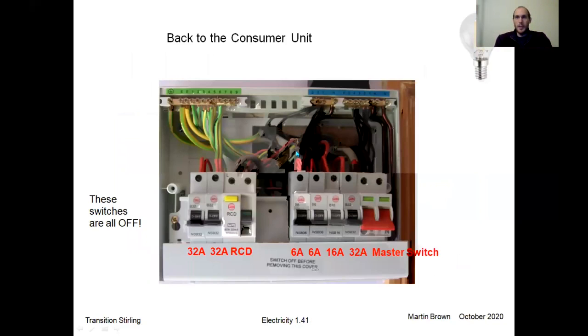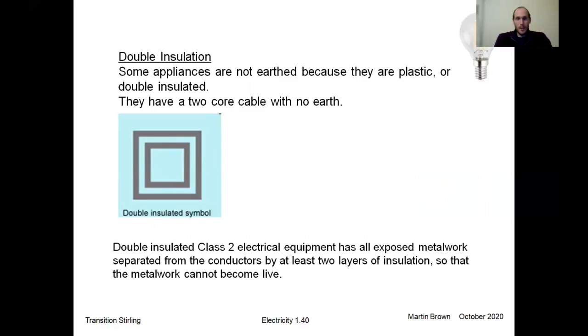Add to that, Martin, that symbol will appear on your appliance, usually on the base or molded into the actual body of it if it's a plastic casing. So if it doesn't have an earth, check that it's got that symbol. If it doesn't have that and it doesn't have an earth, again, it should be okay if it's mostly plastic. Yeah, sometimes it'll say class 2 insulation or something like that as well. But that's the symbol that's on it. That's right. Yeah.